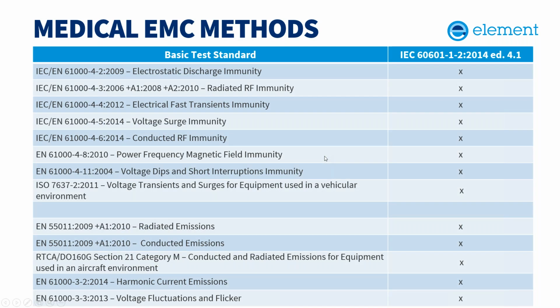So there are 7 base immunity tests in 60601-1-2 that nearly every product is going to need. Electrostatic discharge, radiated and conducted RF immunity, electrically fast transients, voltage surge, power frequency magnetic field, and voltage dips and interruptions. There's also ISO 7637-2, which is voltage transients in the automotive environment. So that's anything that's going to be plugged into DC power in an automobile and connected basically to that battery.